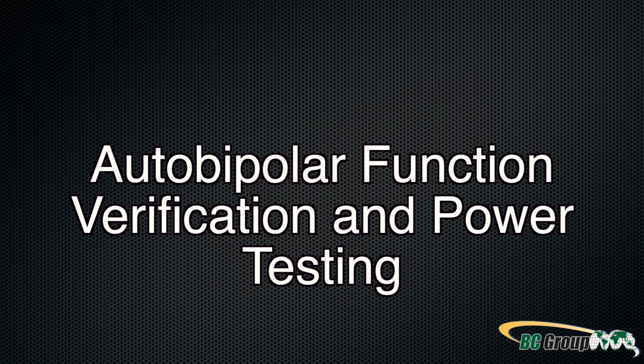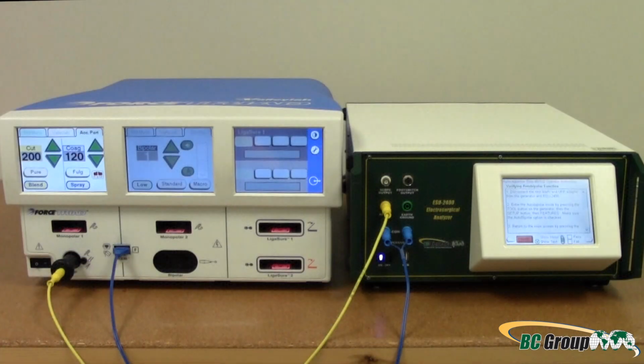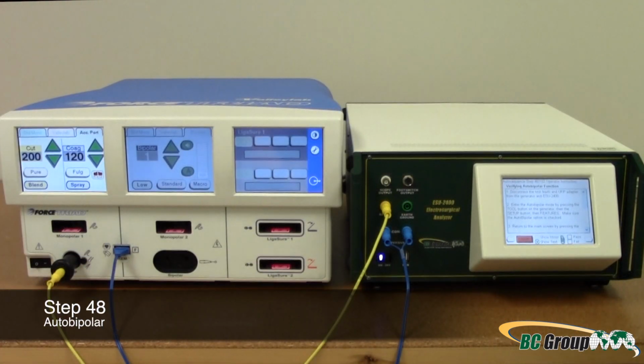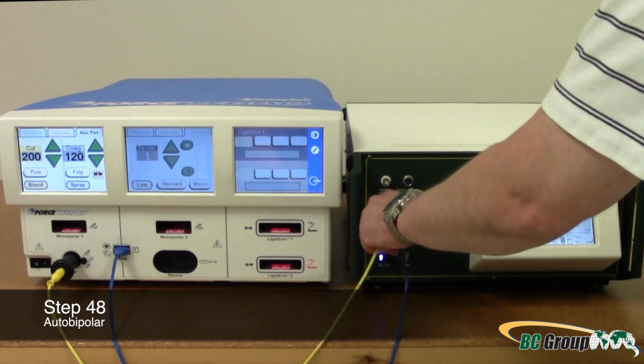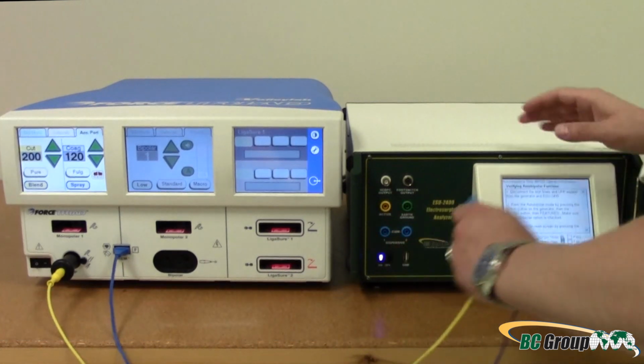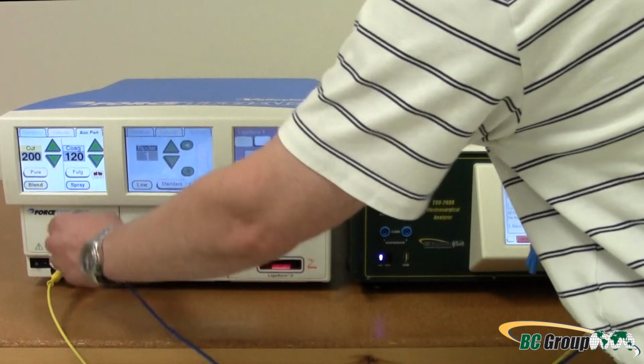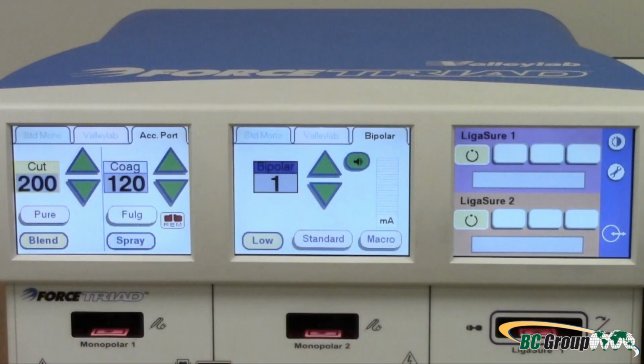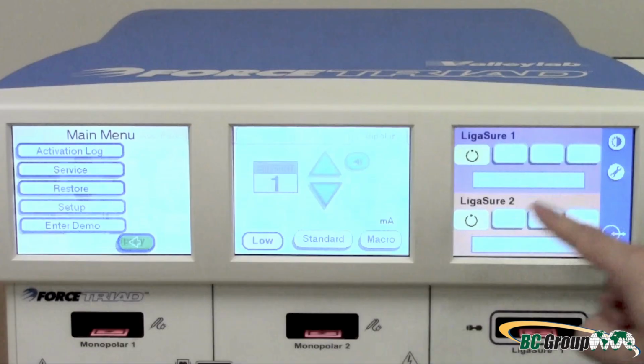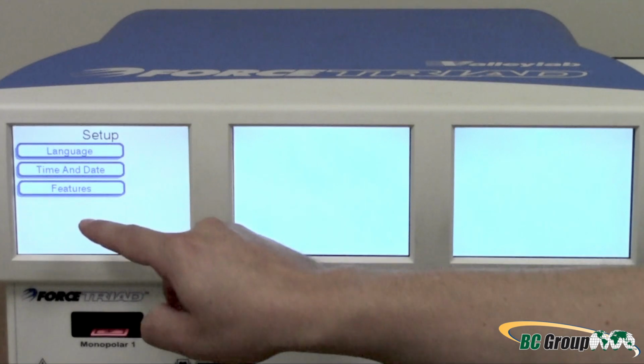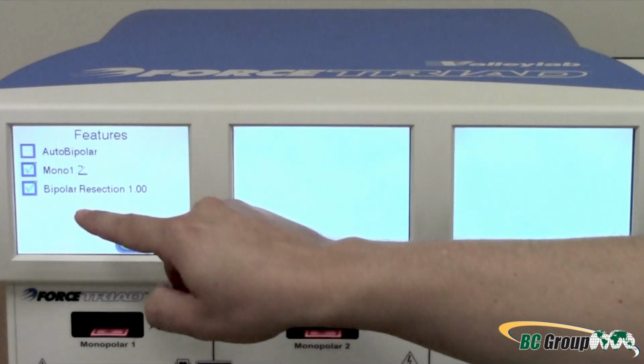Autobipolar function verification and power testing. Step 48. Autobipolar. Disconnect the test leads in the UFP adapter from the generator and the ESU-2400. Enter autobipolar mode by pressing the Tool button on the generator, then Setup and Features.